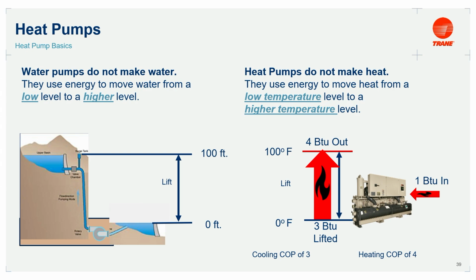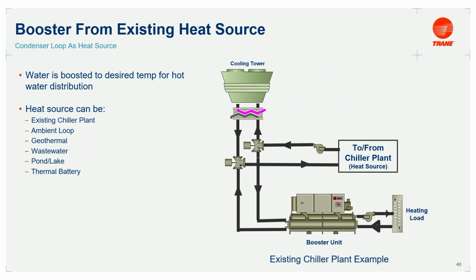Right off the bat, water pumps don't make water — everybody knows that. Heat pumps don't make heat either; they use energy to bring low temperature heat to a higher temperature. That lift is described as the difference between the leaving water temperature out of the condenser and the leaving water temperature out of the evaporator.